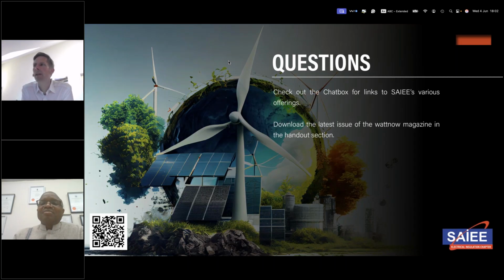Yes, sir, I can answer that. The first question was about leakages and how we determine them. Unfortunately, there are some leaks in the equipment. Eskom adheres to a spec of a 0.5% limit of gas leaks which is allowed. We monitor on a monthly basis all the top-ups on the GIS. Every single top-up is logged against the compartment, so we know exactly what amount of SF6 leaked out.